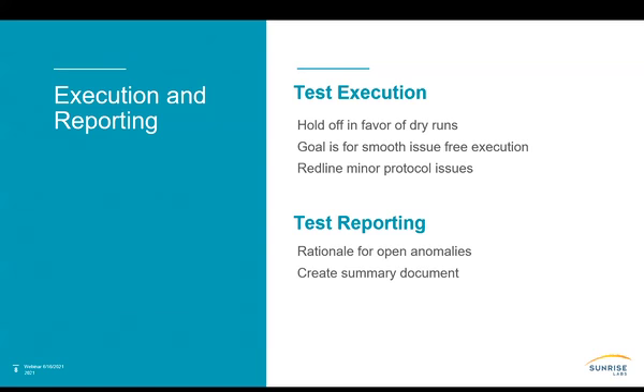And for test reporting, here at Sunrise we are huge fans of a summary report. We feel that it really saves a lot of time. What we do is we create the test record, which is really the individual protocol report. Then we create a summary report that encapsulates all of the protocols. Let's pretend that you have 10 protocols for your system. You would have 10 individual test records, which represent the protocol report for each of those protocols. And then you have one summary report that sits on top, summarizes everything found, and points to each of the individual protocols. It's a very easy way to understand.